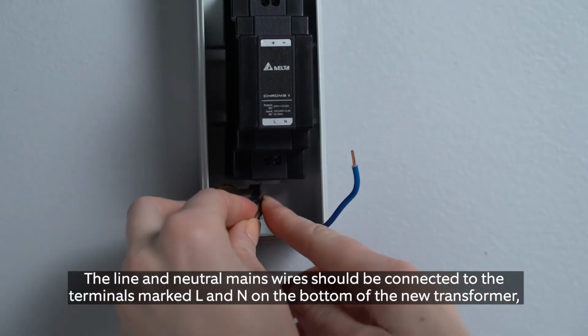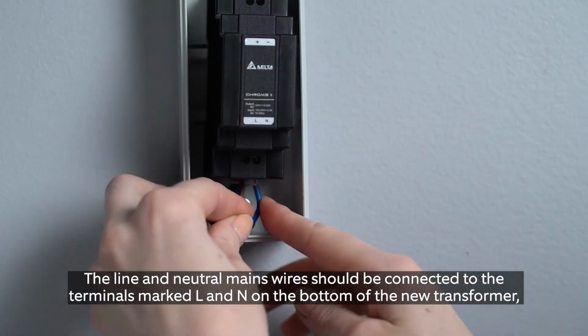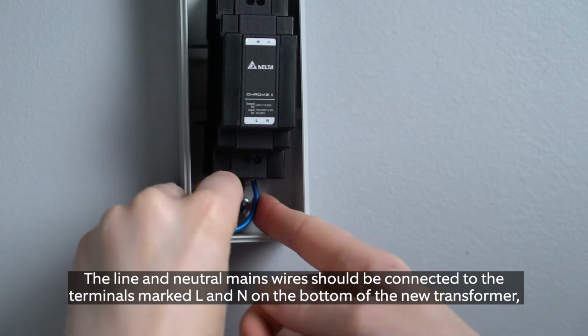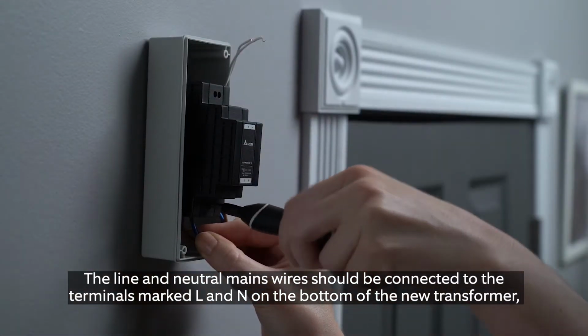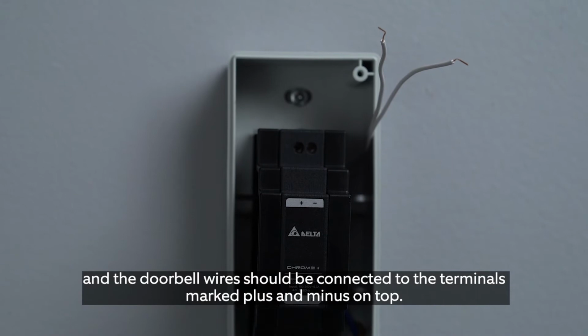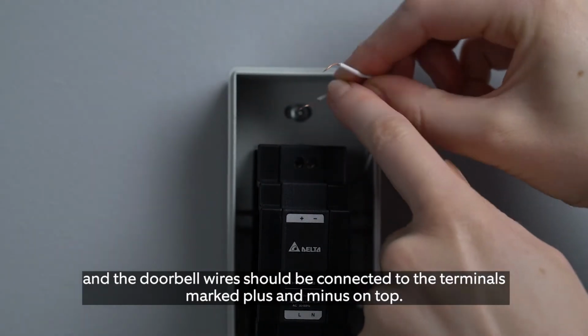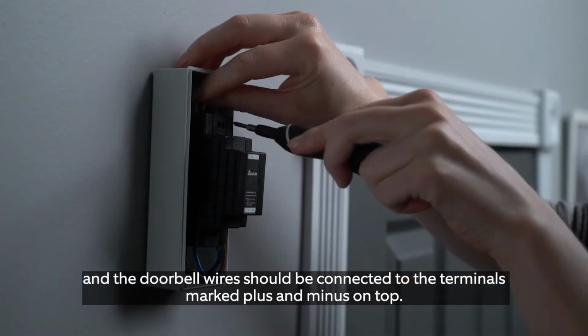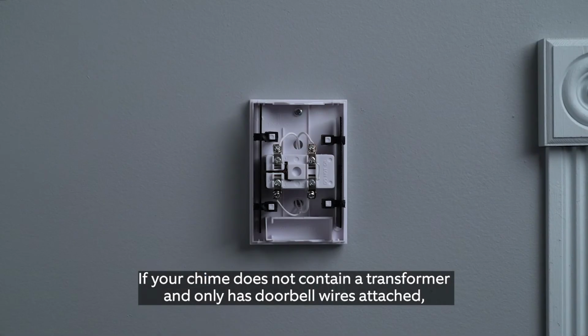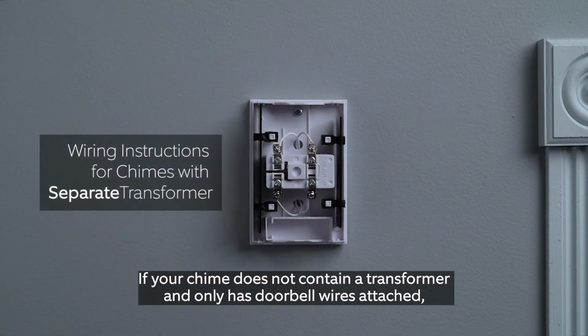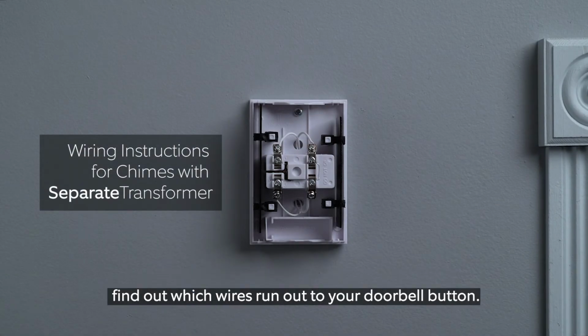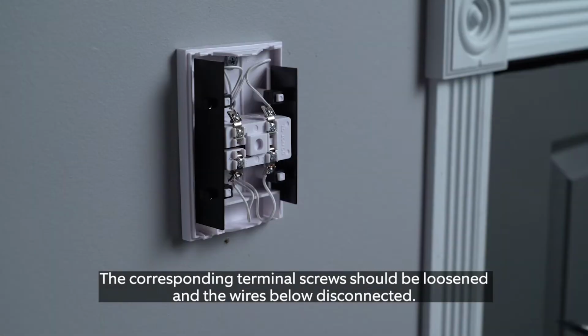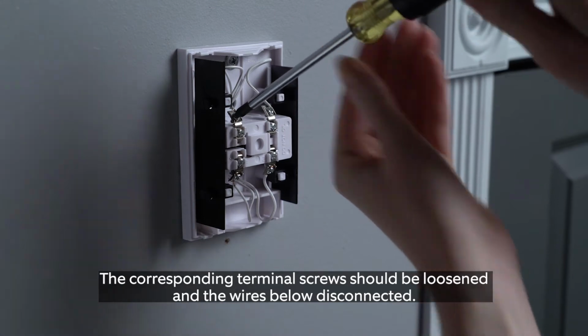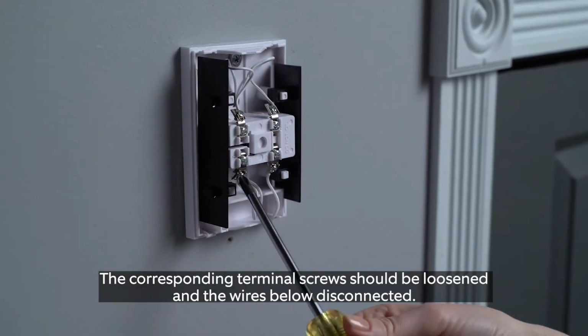The line and neutral mains wires should be connected to the terminals marked L and N on the bottom of the new transformer, and the doorbell wires should be connected to the terminals marked plus and minus on top. If your chime does not contain a transformer and only has doorbell wires attached, find out which wires run out to your doorbell button. The corresponding terminal screws should be loosened and the wires below disconnected.